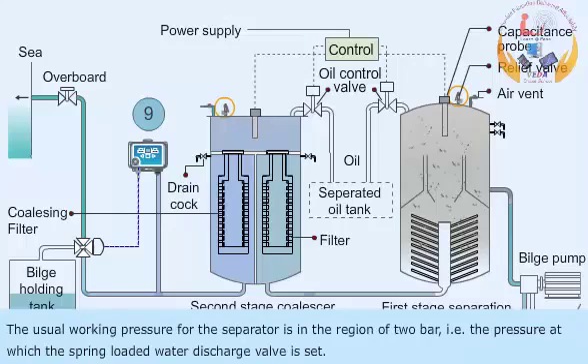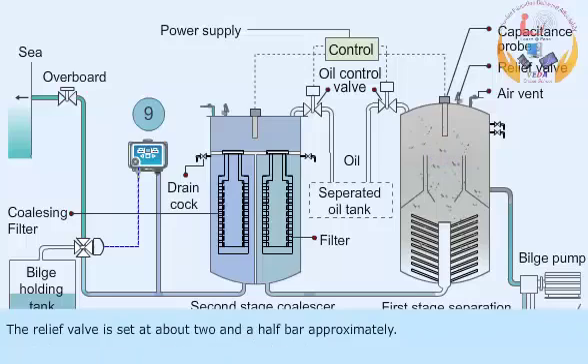The usual working pressure for the separator is in the region of 2 bar, that is, the pressure at which the spring-loaded water discharge valve is set. The relief valve is set at approximately two-and-a-half bar.